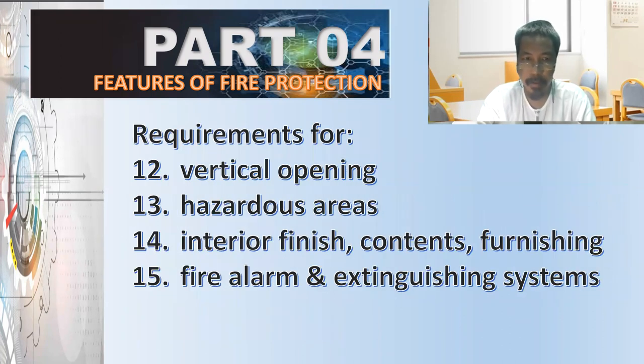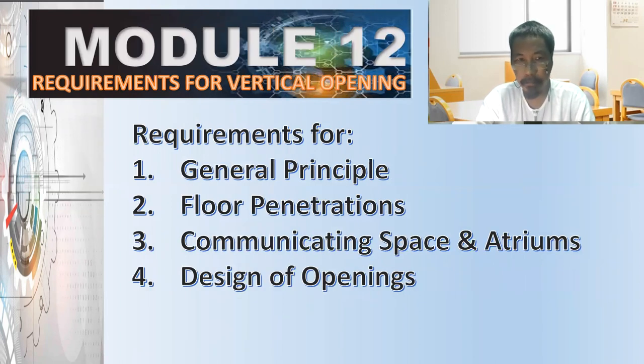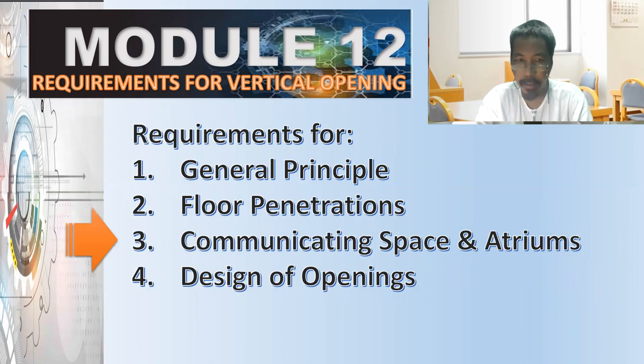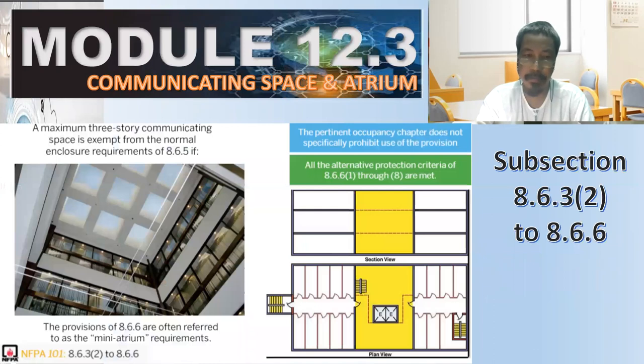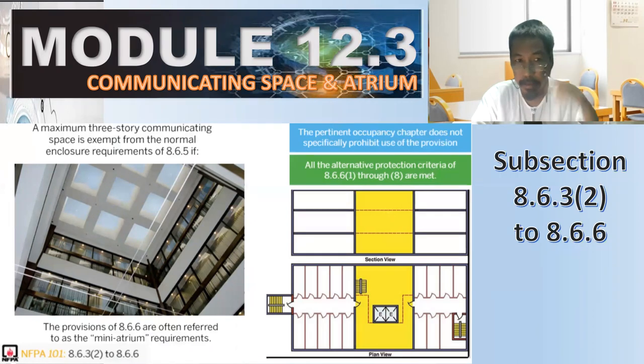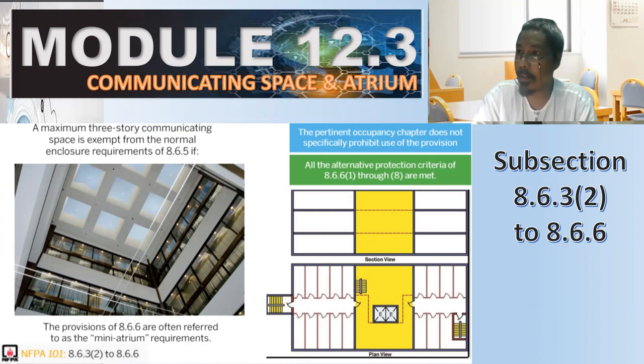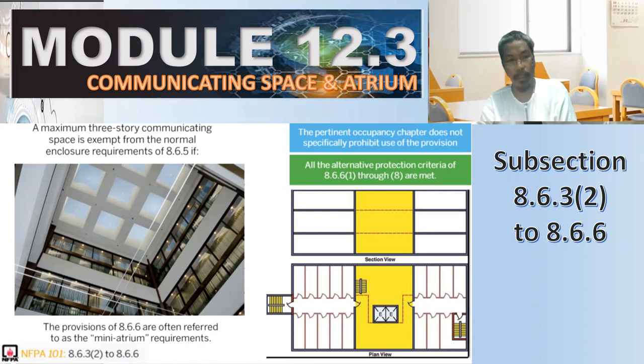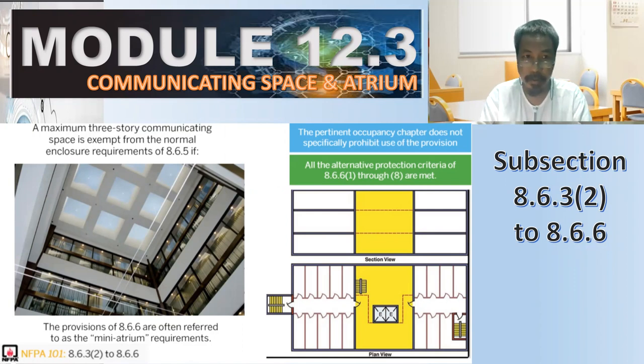So, features of fire protection — we have four major parts and we are currently on module number 12. Under this module, we have four subtopics. We are now going to discuss number three: communicating space and atrium. A maximum three-storey communicating space is exempt from the normal enclosure requirements of 8.6.5. As we can remember, there is a threshold from the last video about four storeys. If the structure is only three-storey, the communicating space is exempt from the requirements for normal enclosure.